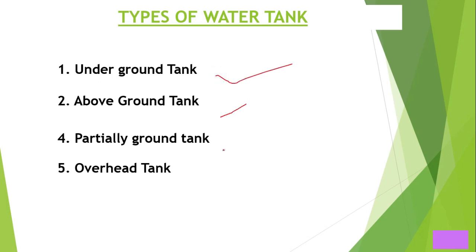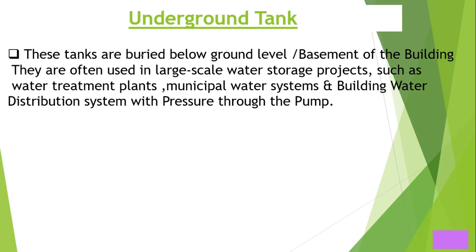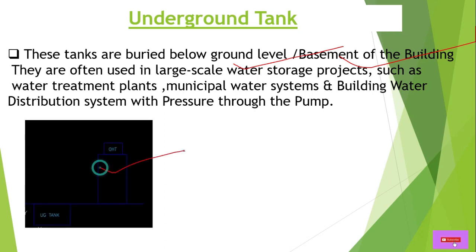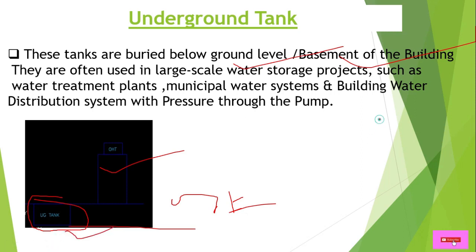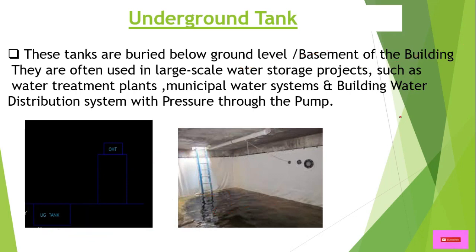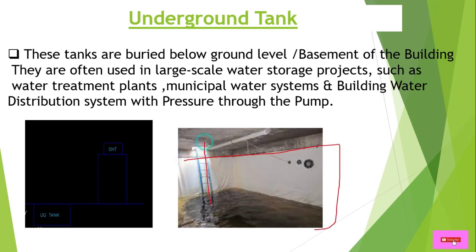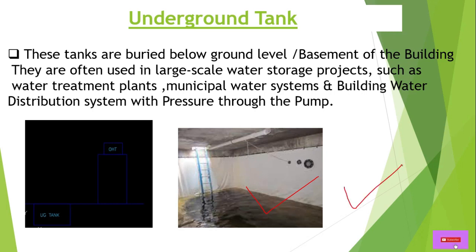Now let's discuss tank types one by one. Underground tanks are buried below ground, typically in the basement of the building. For hotels and other buildings, tanks are usually in Basement 2 or Basement 1. The underground tank has a riser, an overflow line, a water filling line, and a drain at the bottom.